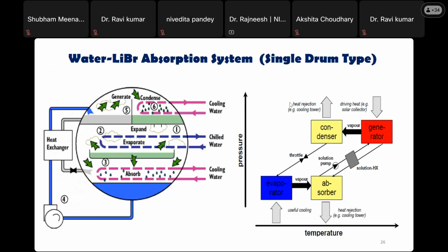In the generator, heat energy is applied for the regeneration purpose. Heat is given to the generator, and the solution is at high pressure. Then vapor is released and condensed, and throttled, meaning the area increases and temperature decreases, so it becomes available at low pressure and low temperature, the least pressure and temperature in the system, giving it maximum potential to absorb heat from the space.